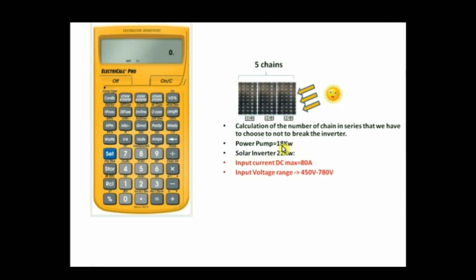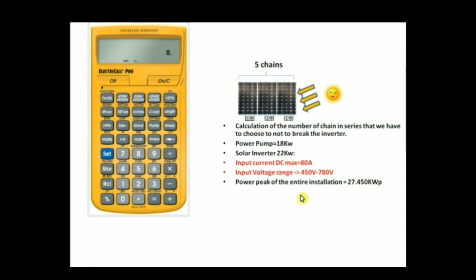We have the pump power equal to 18 kilowatts and the solar inverter power equal to 22 kilowatts. The power of the inverter must be greater than the power of the pump so it can support the pump load. According to the pump power of 18 kilowatts, we're going to need 27.45 kilowatt-peak of solar power to feed our panel. You can see how to calculate this value with ElectriCalc Pro in the last tutorial.